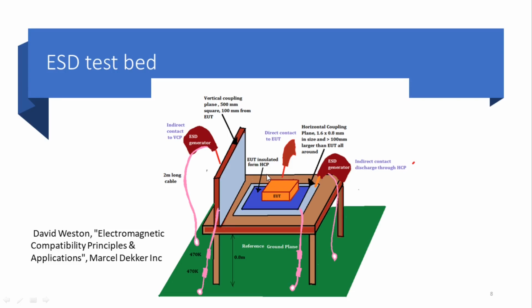While the third one, which is through the air gap, this gun could be left at a certain distance from the equipment under test, and the waveform could be injected at a certain distance from the equipment under test, which means that you don't directly point the tip of the gun onto the equipment, but a certain distance away.